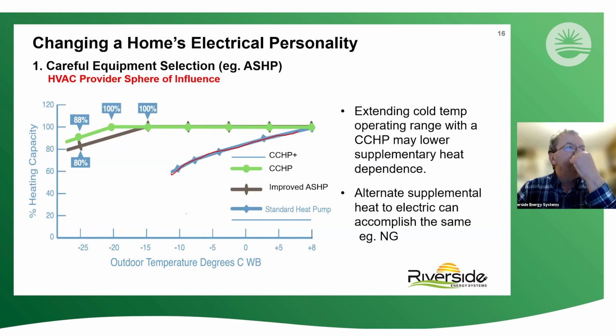If, on the other hand, we spent some extra money and we chose a cold climate heat pump, which are getting better and better, some of them can operate down to -20 and lower and still have a pretty decent coefficient of performance before they need electric boost. So this means that in some climates, like say Vancouver Island or the Lower Mainland, you could potentially not need electric boost at all, which will dramatically lower the service demand. So that's one thing we can do.